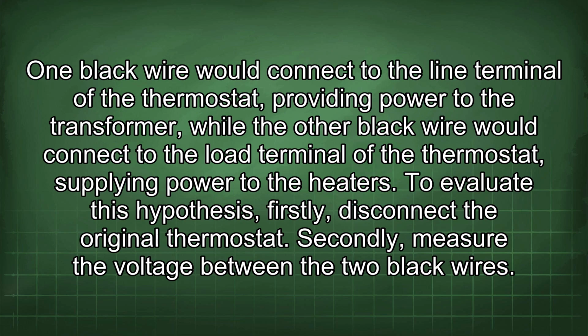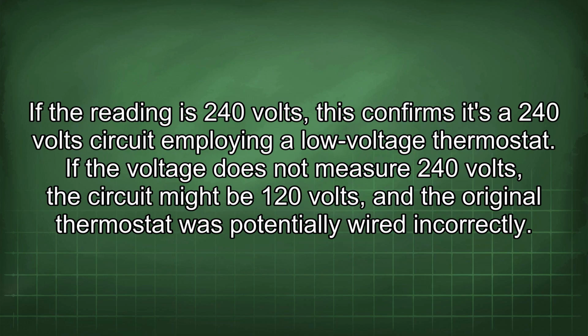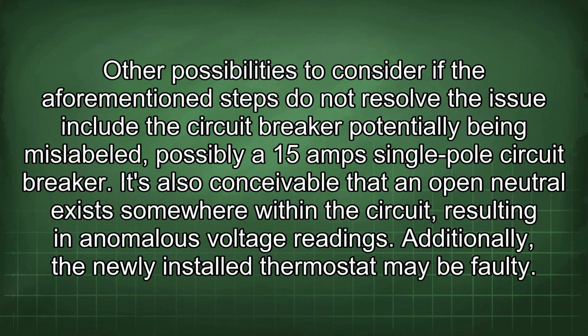To evaluate this hypothesis, firstly, disconnect the original thermostat. Secondly, measure the voltage between the two black wires. If the reading is 240 volts, this confirms it's a 240 volt circuit employing a low voltage thermostat. If the voltage does not measure 240 volts, the circuit might be 120 volts, and the original thermostat was potentially wired incorrectly.